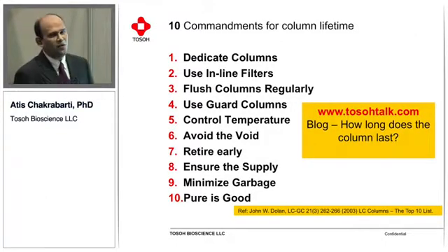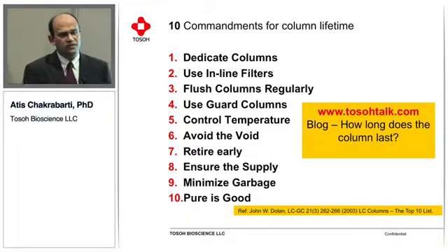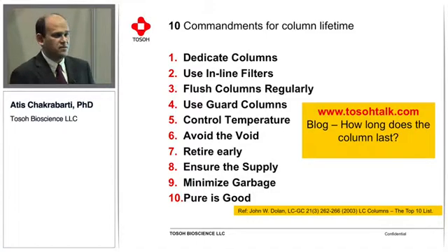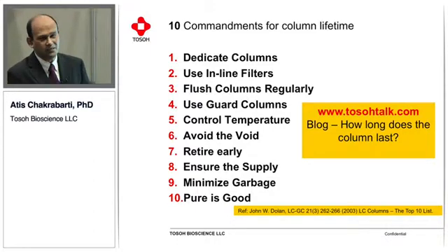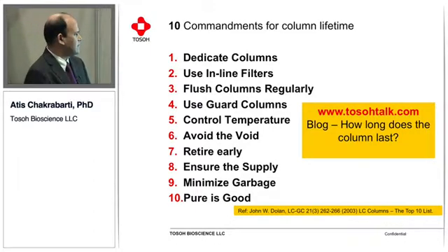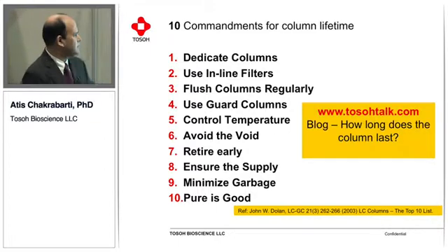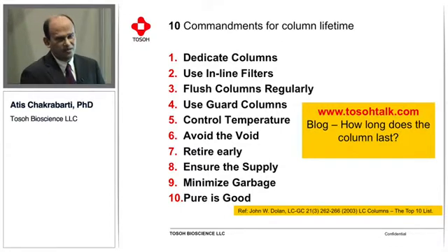Next slide, please. Now, I got this particular one from LCGC. You know, John Dolan, he is very famous. He writes so many different articles, and one was 10 commandments for the column lifetime. And definitely all of these are very important, and we try to take care of all these as much as possible, and that helps in increasing the column lifetime. So dedicate the column. Particularly dedicating the column is more important when you are using some kind of additives. Using in-line filters, flush column regularly, guard columns.